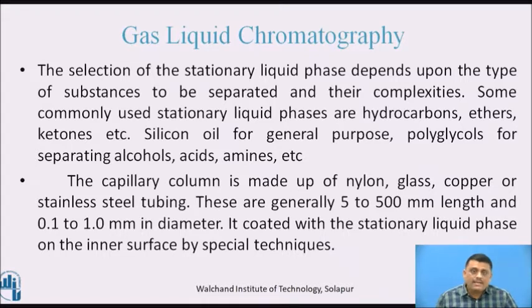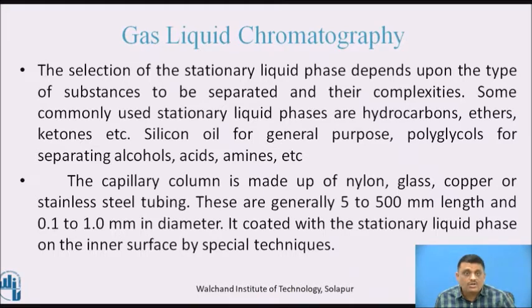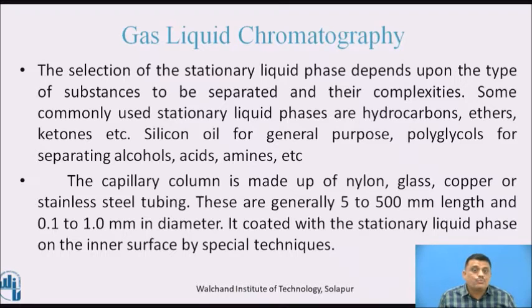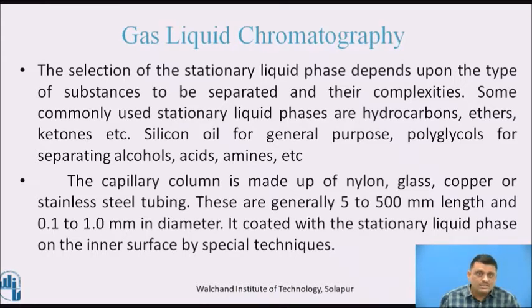The capillary column is made up of nylon, glass, copper, or stainless steel tubing. These are generally 5 to 500 mm in length and 0.1 to 1 mm in diameter. The inner surface is coated with the stationary liquid phase by special techniques.